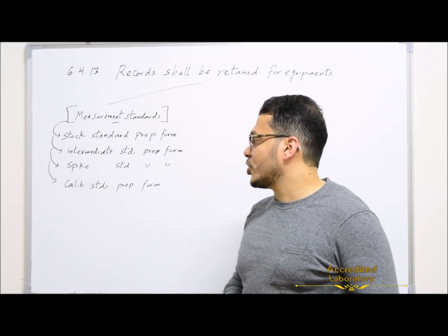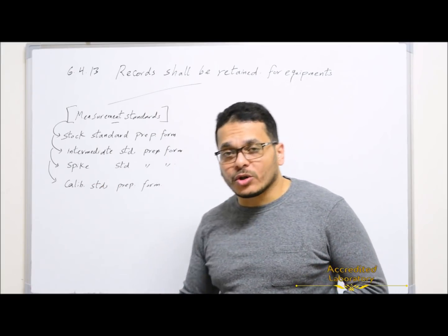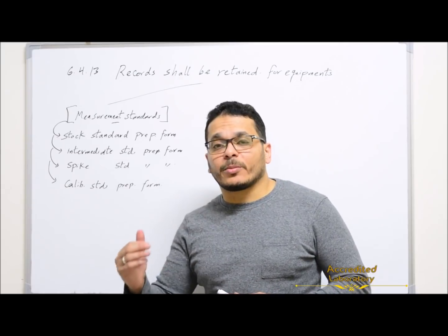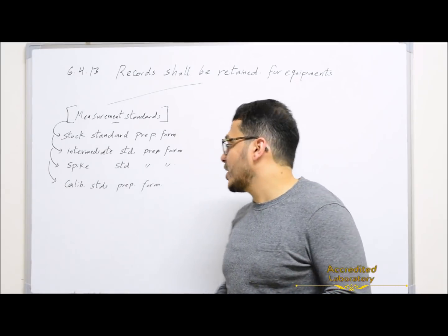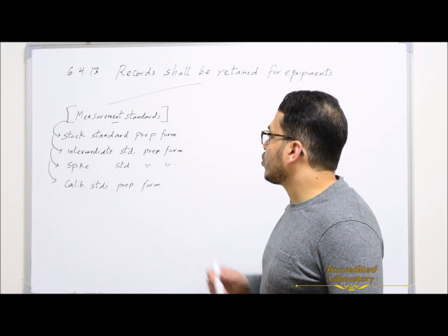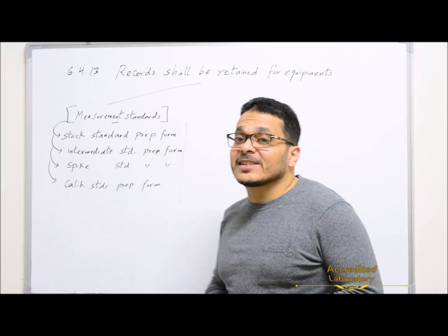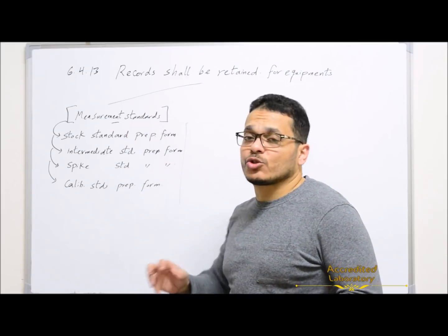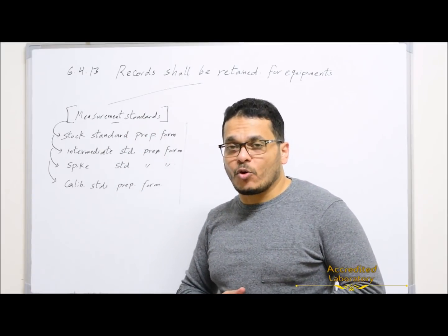Calibration standard preparation form should also be recorded. All calibration standards that you prepare, even daily or after 3 months, you should record, and you should always have the expiry dates for these standards recorded in these forms.